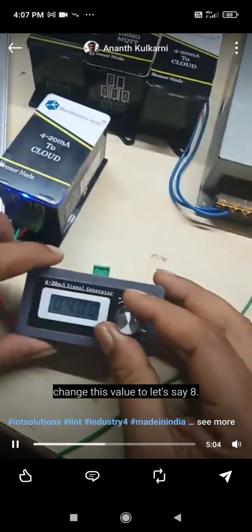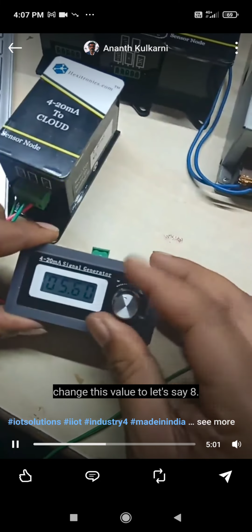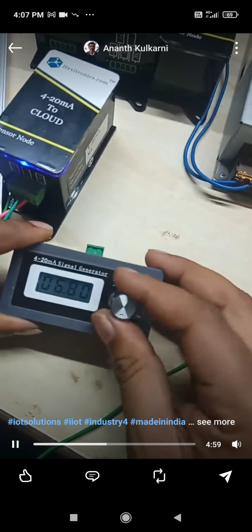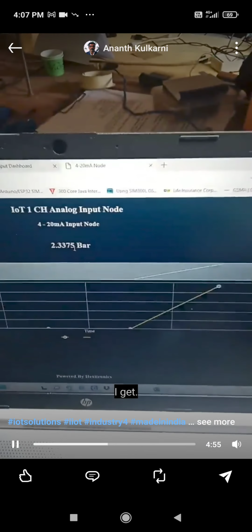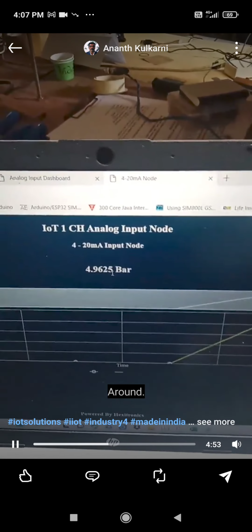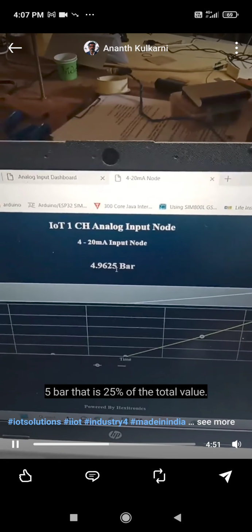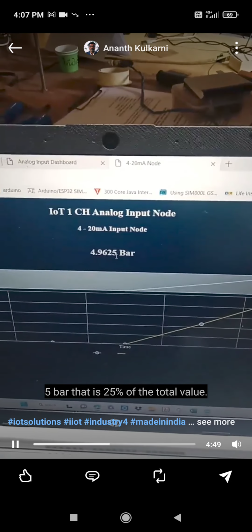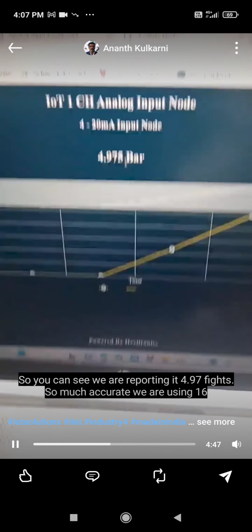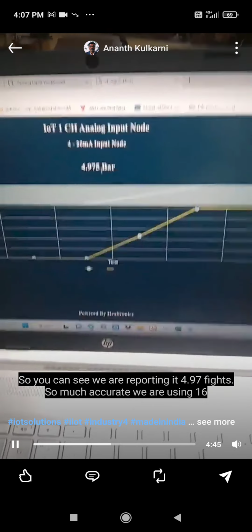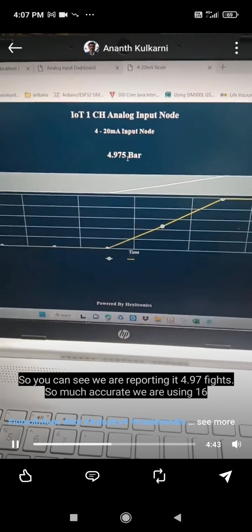If I change this value to, let's say, 8 milliamperes, I get around 5 bar. That is 25% of the total value. So you can see we are reporting 4.975. It's so accurate. We are using 16-bit ADCs inside.